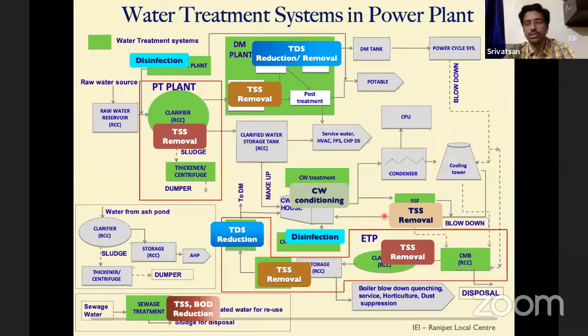Any water which is stored in a tank is susceptible to microorganism growth or biological growth. So we need to keep a level of chlorine or some oxidizing agent concentration present in this system, so that biofouling does not happen. This is done by the chlorination system basically. It is done in the cooling water cycle and also in the pre-treatment system area.